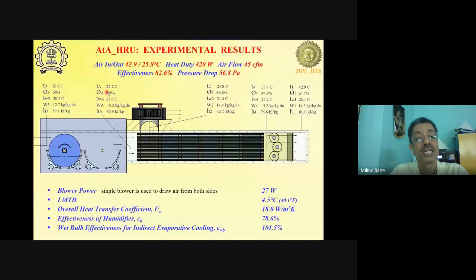In this way, the air temperature would be brought down to 22.2 degrees centigrade before it goes into the heat exchanger, where it is able to cool the air from 42.9 degrees to 25.8 degrees centigrade. And now this 25.8 degrees centigrade outdoor air, fresh air, which is pre-cooled, is now let into the indoor spaces. Now, note that the humidity of this is high. Now, to bring this from here to this, the conventional air conditioning or liquid desiccant based system could be used to do that job.